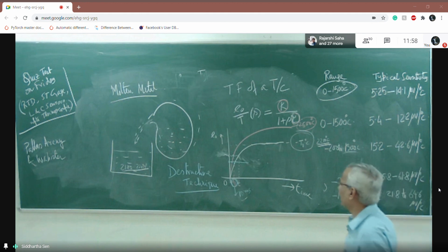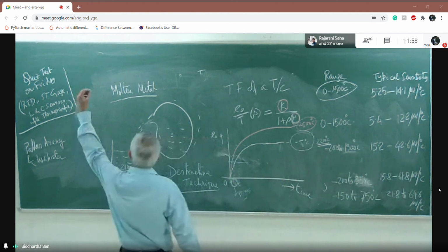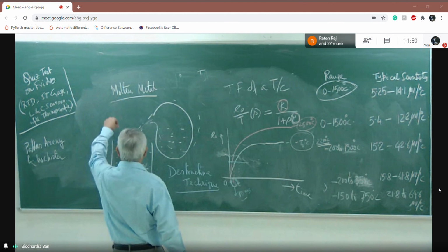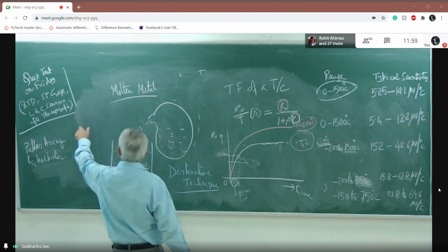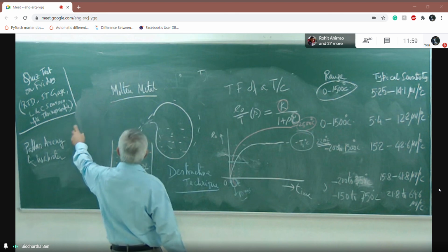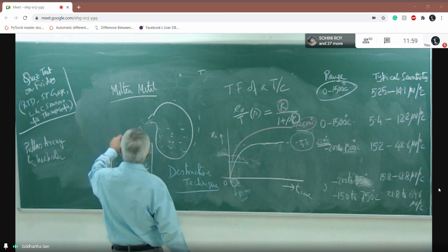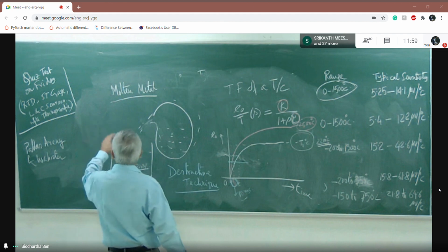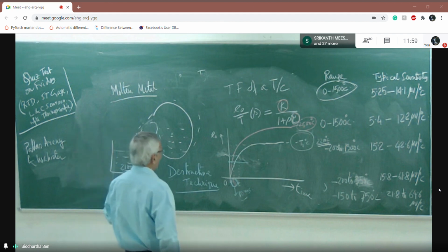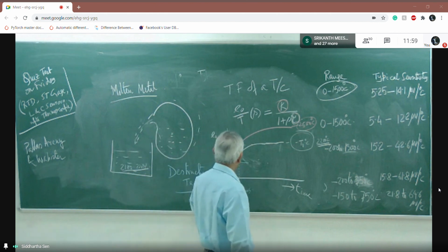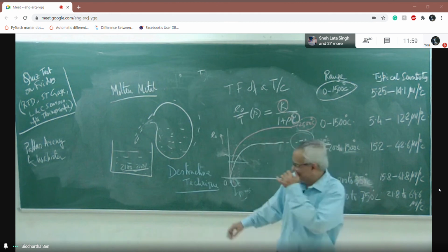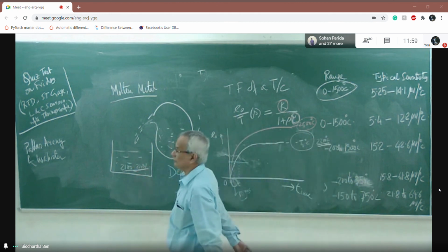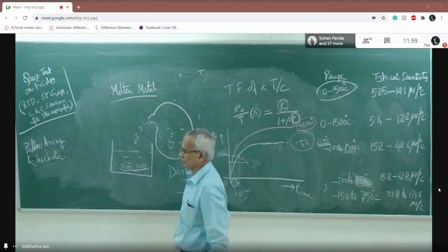They drop a thermocouple on a long wire and see how the thermocouple voltage is changing. After some time it will melt and be destroyed. But from the trajectory during that time, I can say what the temperature of the furnace or molten metal is.